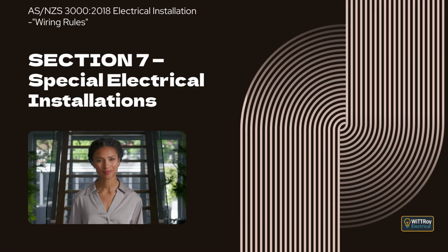7.5.8.1, Main switches. This clause clarifies that the control of supply to an extra low voltage installation must be achieved using main switches that operate in all unearthed conductors, ensuring complete disconnection of the supply when operated.